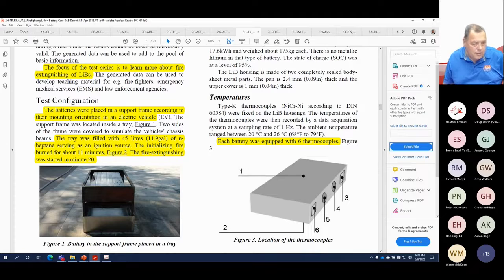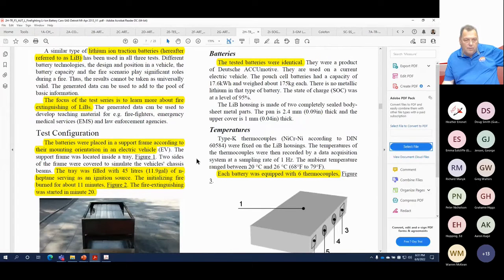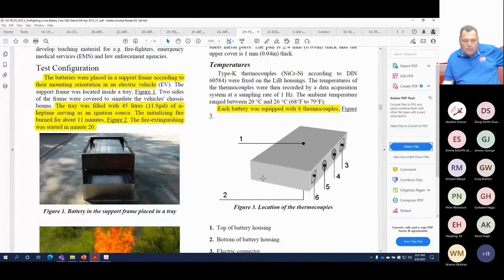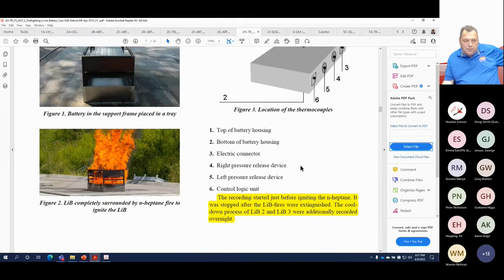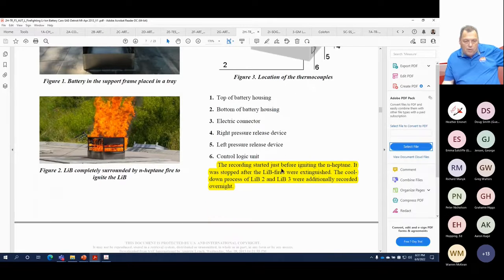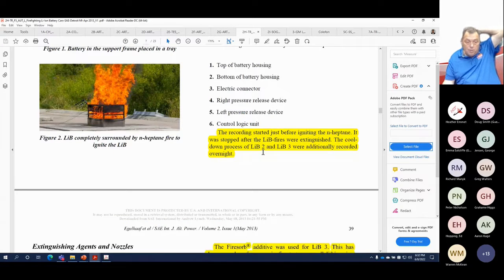These were the test configurations where they put the batteries over top of heptane. The tray was filled with 45 liters of heptane, serving as an ignition source and burned for about 11 minutes. The fire extinguishing was started in 20 minutes. In all tests, the batteries were identical. Each battery was equipped with 6 thermocouples. So this is showing the batteries. Recording started at the beginning of the heptane burn and was stopped after the batteries were extinguished and the cooling process was done.